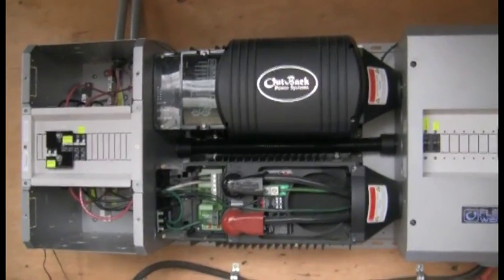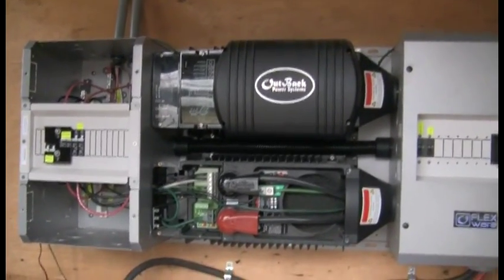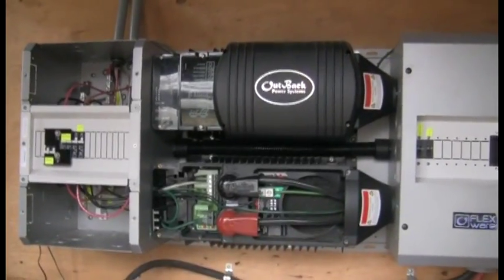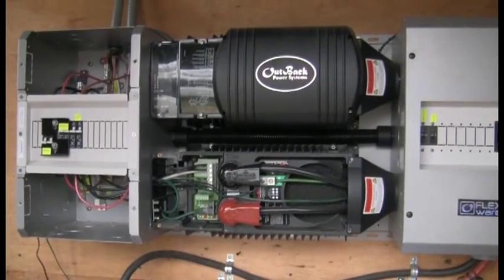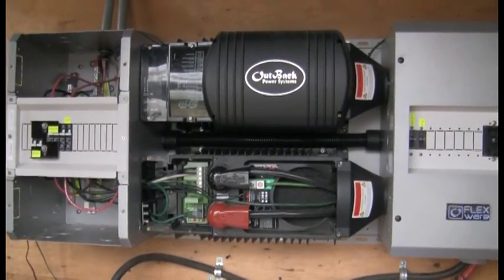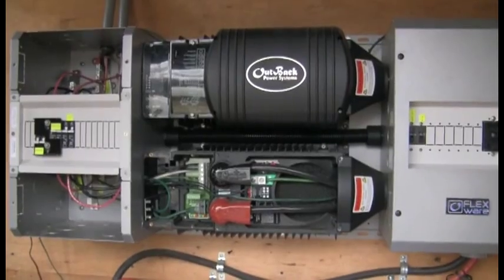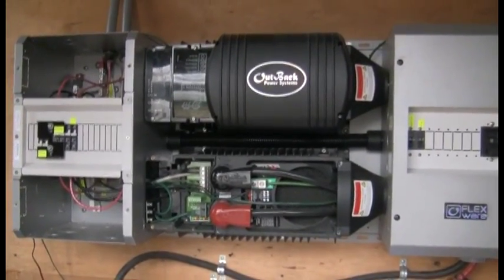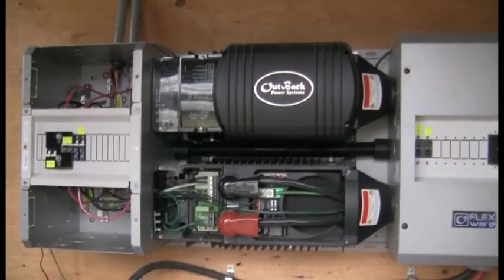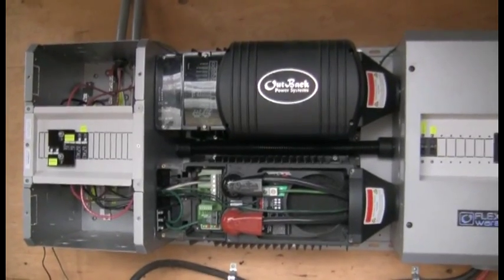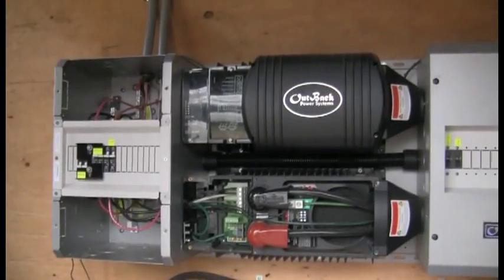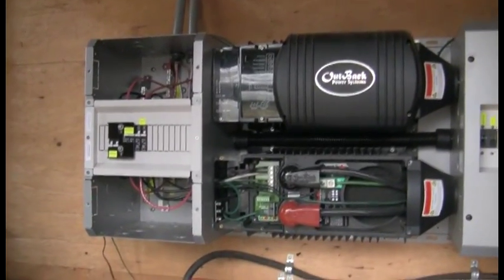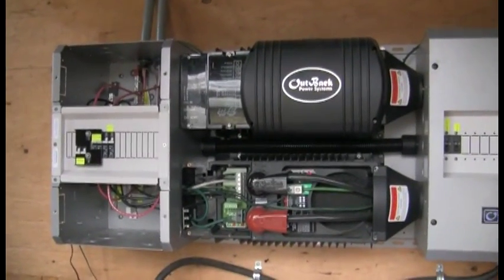Being indoors and not subject to the elements, it was a good match. If you're mounting one of these inverters in an exterior location, especially in high humidity or where pests like bees and wasps might be a problem, you may elect to go with the straight FX, which is a completely sealed unit.